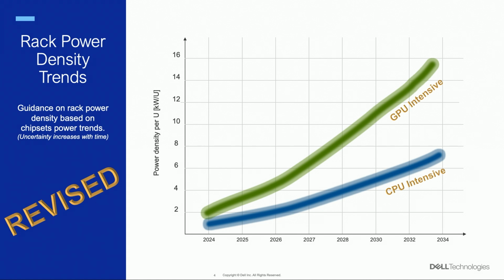If you think those numbers are impressive, translating them into the typical 48-unit HPC rack projects an estimate around 750 to 800 kilowatts per rack. So you understand the size of the problem. This is clearly an extrapolation, subject to errors and variations, but it's still important to set the stage and understand the direction we're taking.